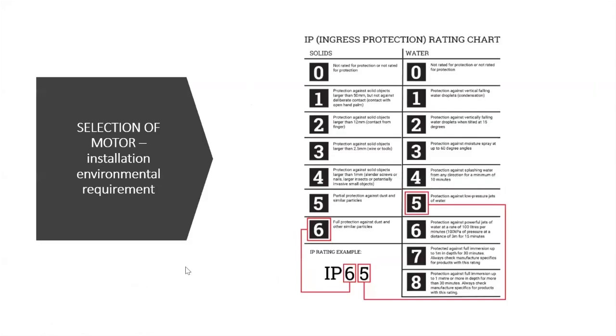So with maintenance in perspective, when selecting motors, you look at the environment you are going to install your motor. Is it a very dusty environment? Will the motor be exposed to chemicals? So based on that, you select your IP rating using the ingress protection chart. For instance, for typically mining industries, an IP66 is okay. For IP66, you see is full protection against dust and other similar particles.